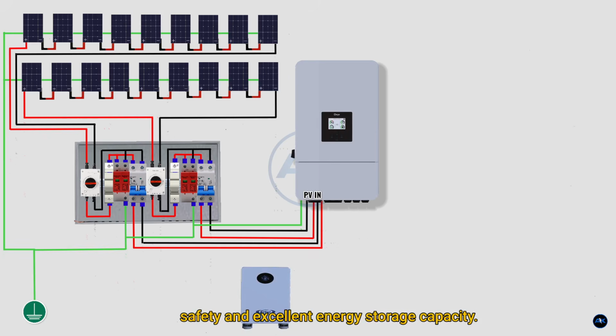Begin by placing the battery in a cool, dry, well-ventilated area. Ensure that the battery cabinet is level and secure, and that there is adequate clearance for airflow and maintenance. Never install the battery in direct sunlight or near moisture. Next, we'll prepare the DC cables.